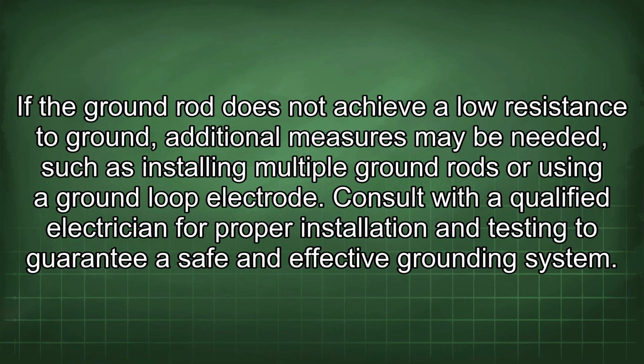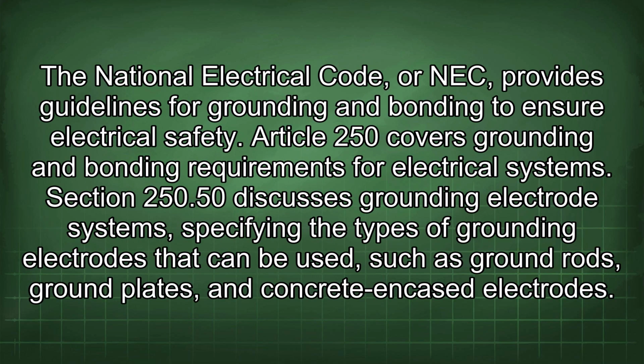If the ground rod does not achieve a low resistance to ground, additional measures may be needed, such as installing multiple ground rods or using a ground loop electrode. Consult with a qualified electrician for proper installation and testing to guarantee a safe and effective grounding system. The National Electrical Code, or NEC, provides guidelines for grounding and bonding to ensure electrical safety. Article 250 covers grounding and bonding requirements for electrical systems.